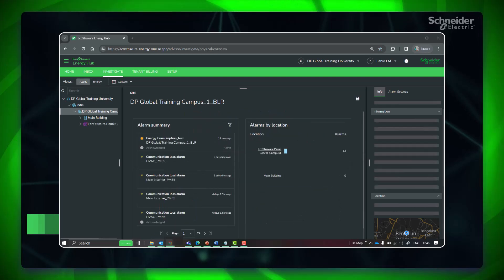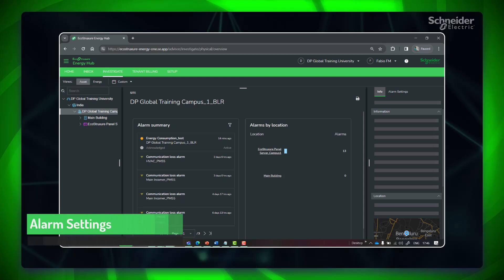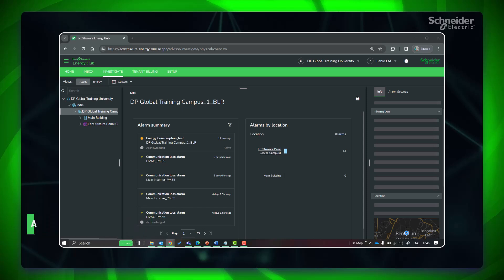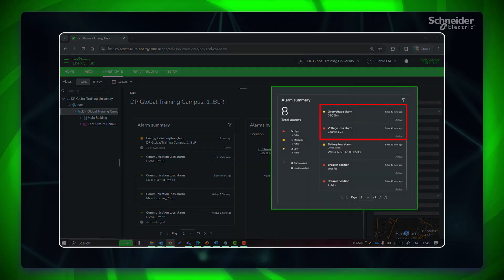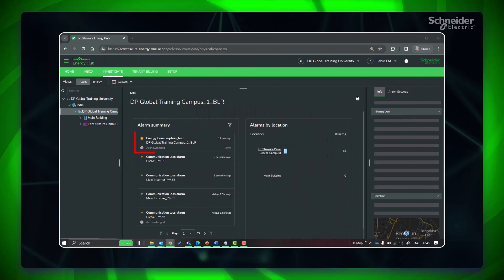Next, let's configure some alarms to stay informed or notified about any exceptional operating conditions in your facility. Energy Hub has mainly two types of alarms: namely device-based alarms, which are configured outside of Energy Hub on the monitoring devices or on the communication gateways, and software alarms, which are configured in Energy Hub based on the modules or subscriptions activated. There are also various categories of alarms based on their functionality. For energy alerts, software alarms are available for energy, water, and gas consumptions, which falls into the category of energy management.